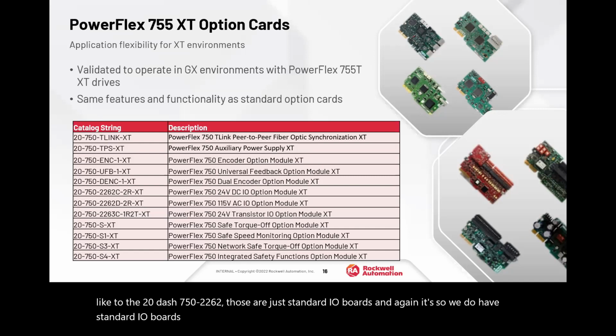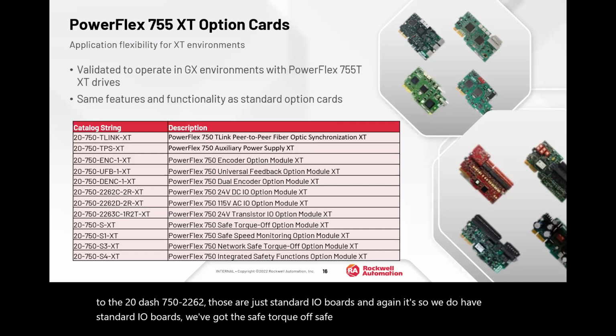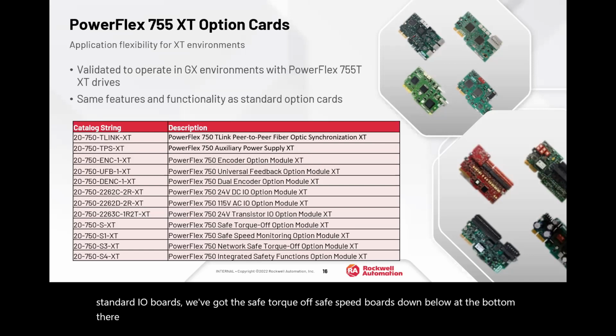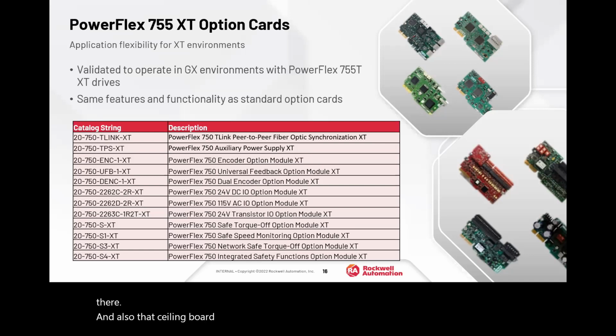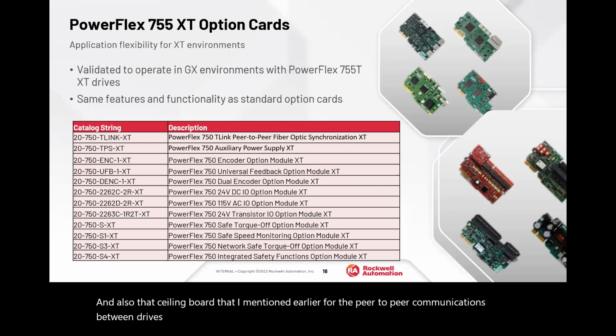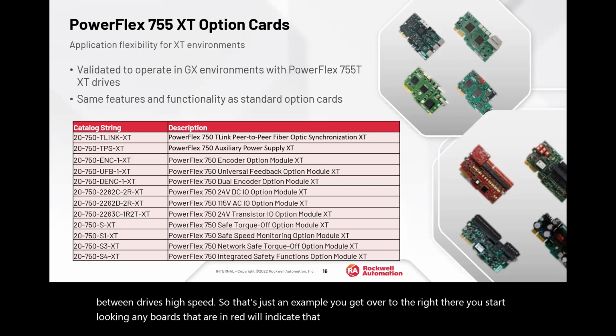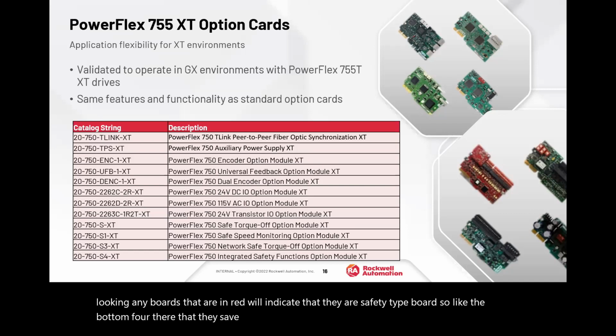We've got the safe torque off and safe speed boards down below at the bottom there, and also that T-Link board that I mentioned earlier for the high speed peer-to-peer communications between drives. So that's just an example. Over to the right there, any boards that are in red will indicate that they are a safety type board. So like the bottom four there, the safe torque off and safe speed, those would be in red when you actually purchase them.